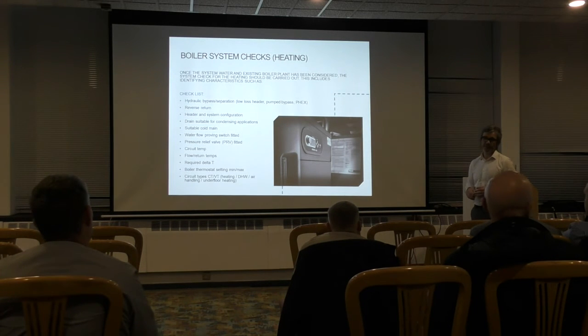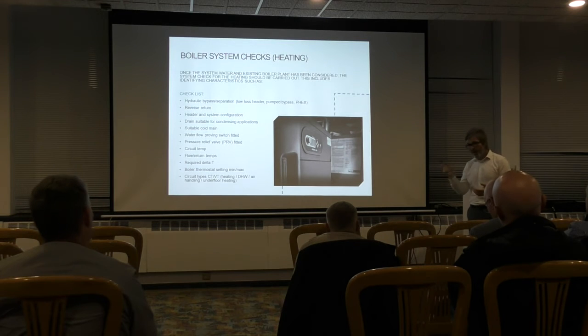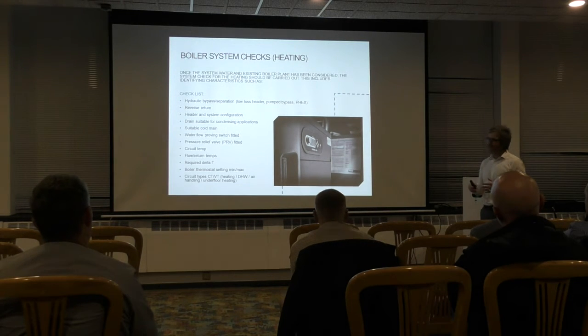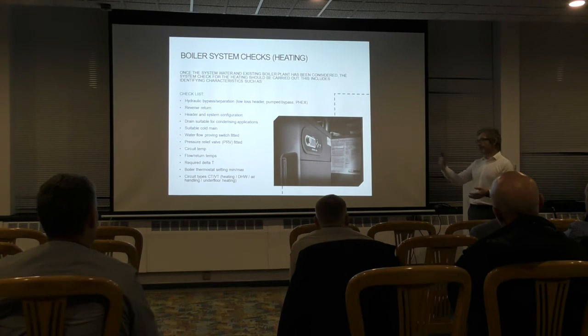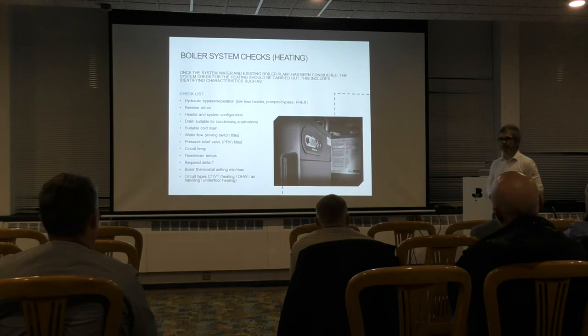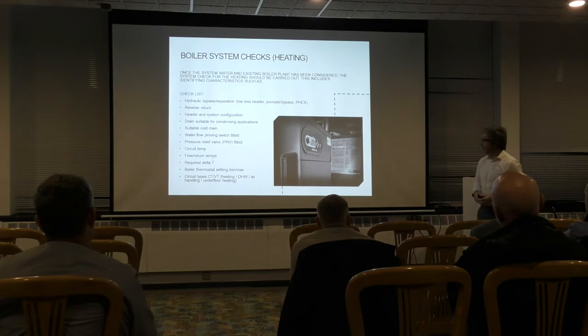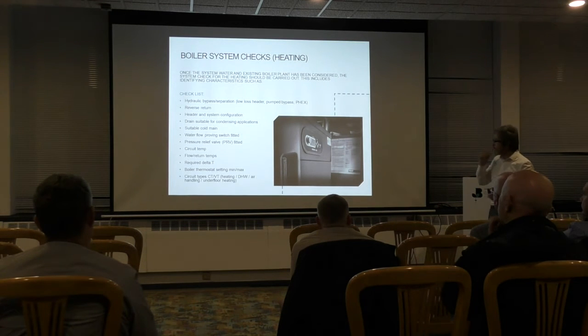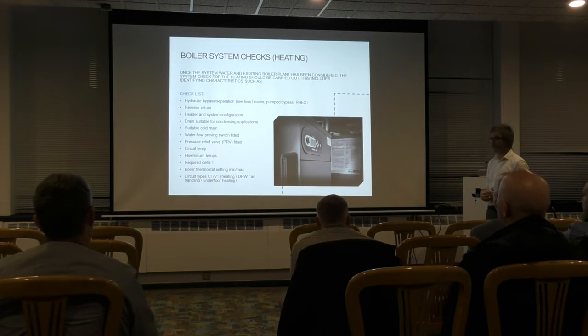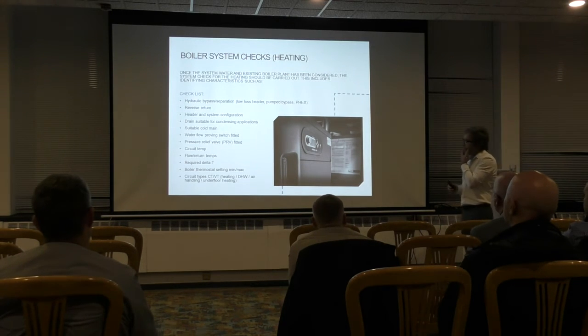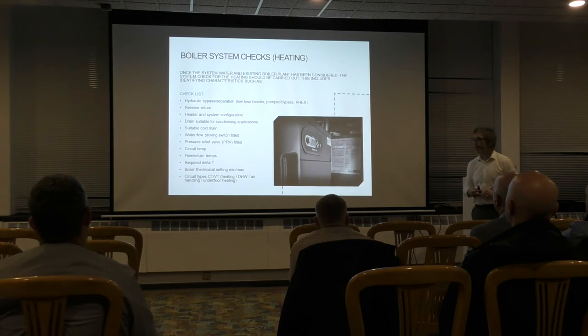Plus as well you can get potential problems with noise because we're trying to put a higher velocity through a smaller waterway. So really I would always say that if you can keep your primary side on a 20 degree delta T, keep those flow rates down, with your secondary side on 11, then you'll get around it. Obviously your boiler thermostat, the minimum and maximum setting of the current boilers and the boilers you're proposing to put in. And the circuit types, I suppose we haven't really spoken about circuit types. Are we looking at what we're serving? So are we serving constant temperature, variable temperature, domestic hot water, that type of thing.